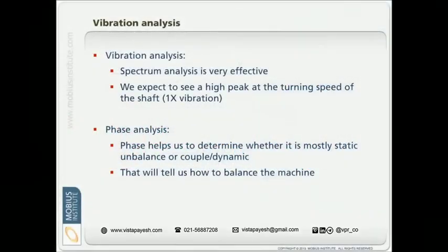Vibration analysis is a powerful tool for diagnosing unbalance. The spectrum is very useful because we will always expect to see a high peak at the running speed or turning speed of the machine, which we'll call 1x vibration, one times running speed. But phase analysis is also very important. It helps us determine that it is unbalanced and helps us understand whether we've got static unbalance or dynamic unbalance, as you'll see with the animations.